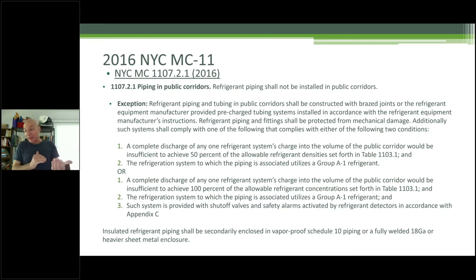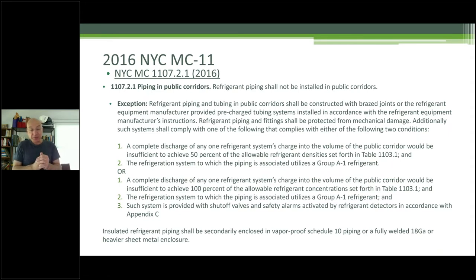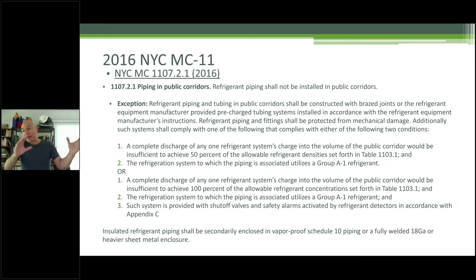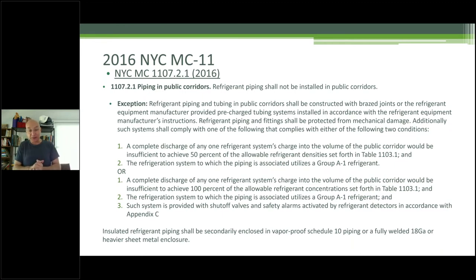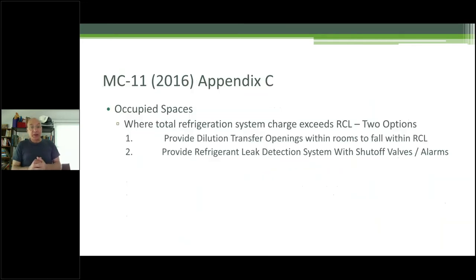The other way — if you really don't want to do the valves — you can run the piping in a vapor-proof Schedule 10 minimum pipe and weld it. Essentially you're saying it's vapor-proof from end to end and you're bypassing the corridor. If there's a leak, the refrigerant is going somewhere, but not into the corridor. And wherever it's going, make sure you're not also exceeding those RCLs.